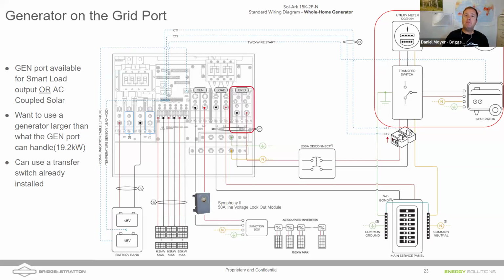The problem is, if we now add a generator onto the system, we can have some complications. Nathan, correct me if I get any of this wrong: in order to curtail the production of AC coupled solar, we have to use frequency shifting. We ramp up the frequency, I think to 62 hertz, right? Those UL 1741 SB compliant inverters, SA as well, yes, SA, thank you. They recognize that the frequency is jumping up and stop production. But when we have a generator, the frequency of the AC bus is dictated by the generator, so we lose that capability of frequency shifting to curtail AC coupled solar charging.